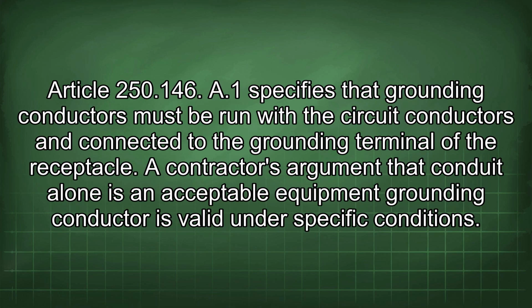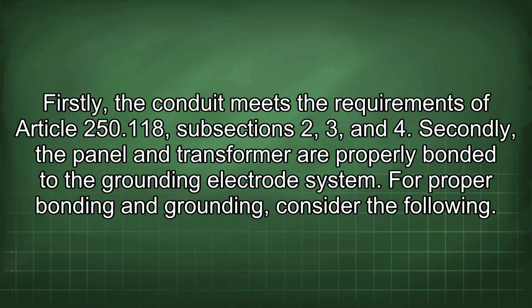Article 250.146(A)(1) specifies that grounding conductors must be run with the circuit conductors and connected to the grounding terminal of the receptacle. A contractor's argument that conduit alone is an acceptable equipment grounding conductor is valid under specific conditions. Firstly, the conduit meets the requirements of Article 250.118 subsections 2, 3, and 4. Secondly, the panel and transformer are properly bonded to the grounding electrode system.